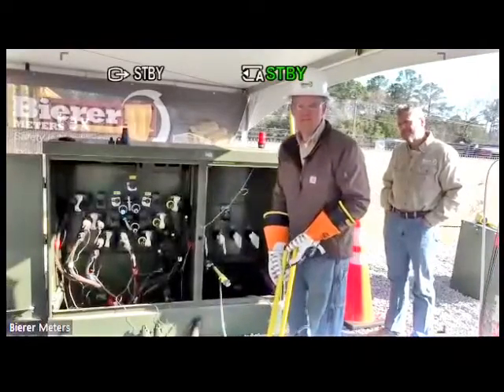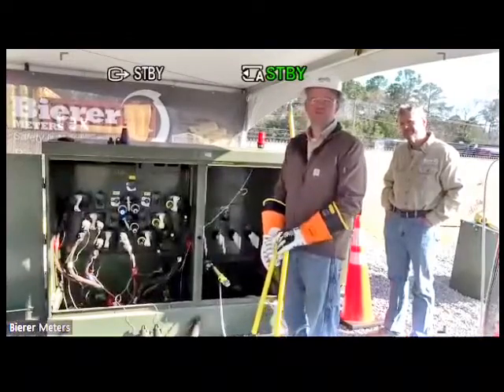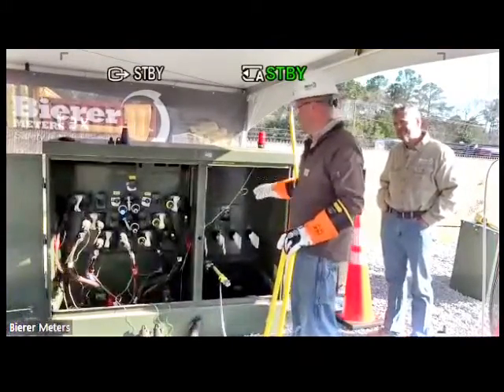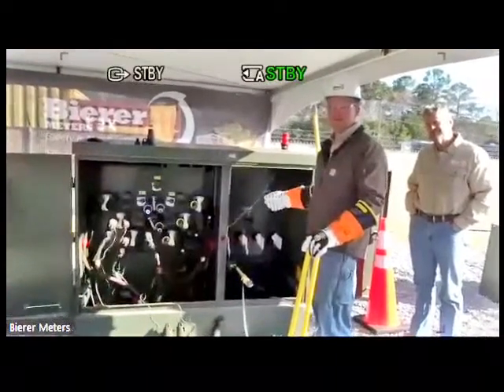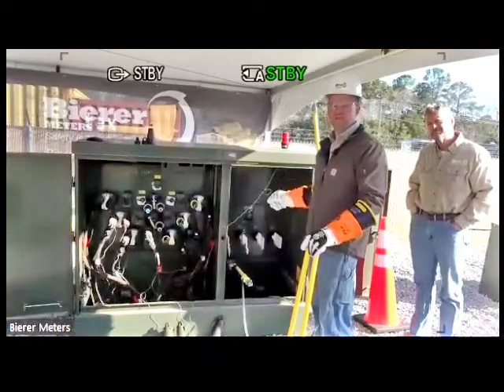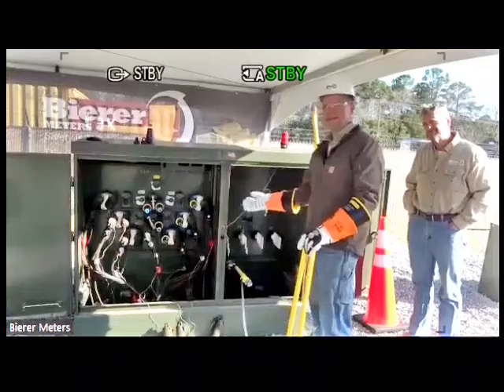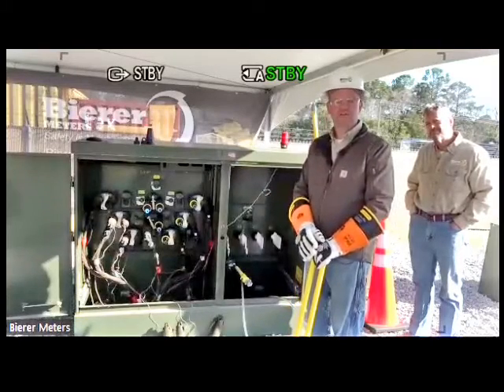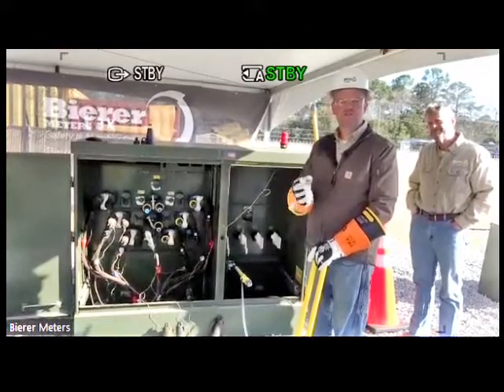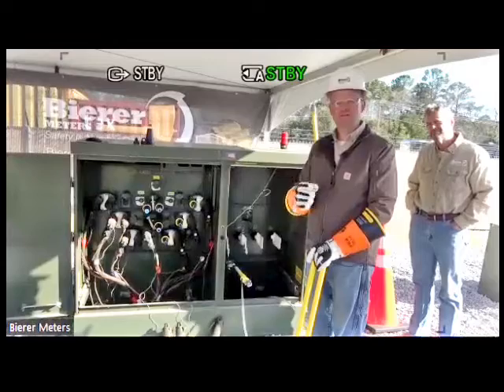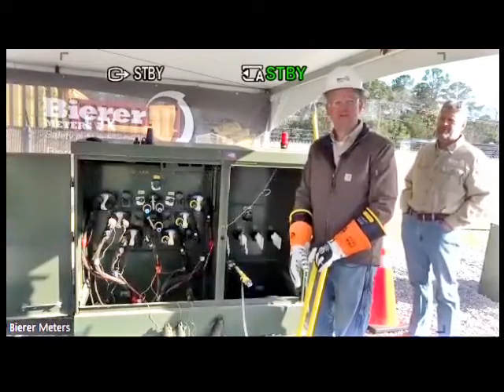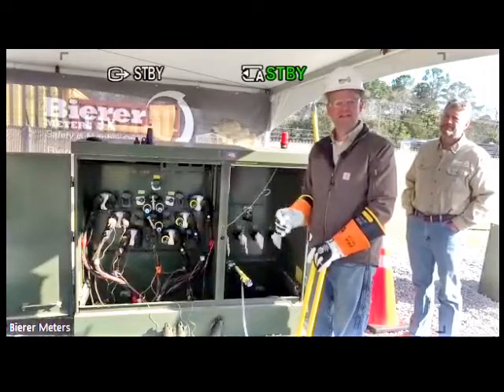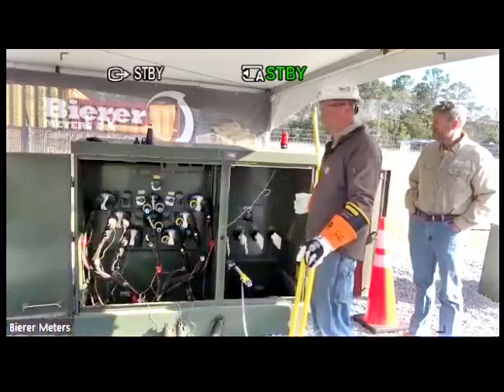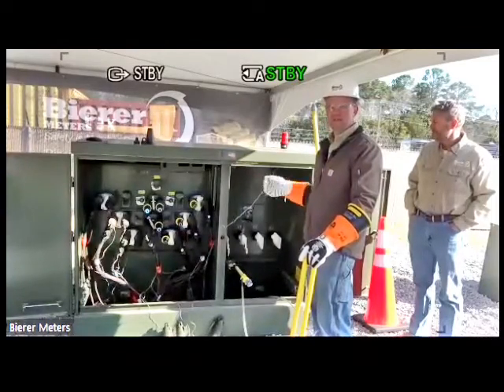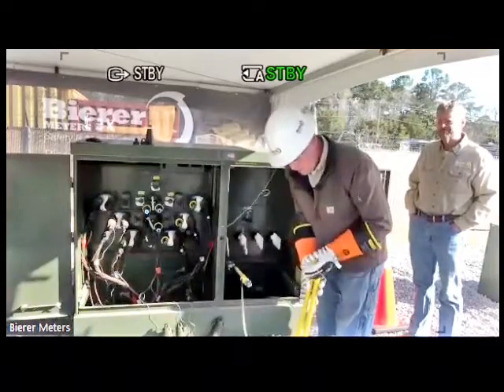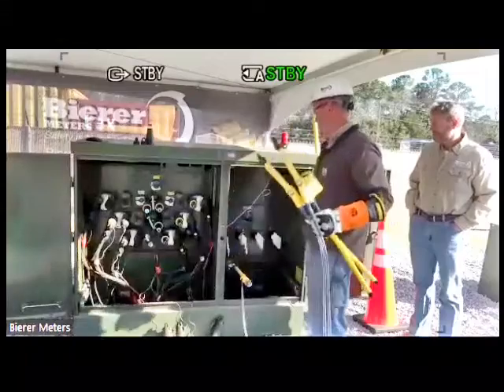All right. So what I would recommend, if you ever utilize this tool versus the tool that you're using now, is that you connect the tool you're using now to the same scenario. And if that tool said counterclockwise, then from that point forward, if your phases went from right to left using this tool, that represents counterclockwise. So you would have to associate it with the tool you're using now, because some of those manufacturers may differ a little bit as far as clockwise, counterclockwise. You would just have to compare this to the tool you're using now to get that designation. But this is telling you the sequence left to right, right to left. So you'd have to, again, compare that to the counterclockwise, clockwise. All right, so that's on secondaries.